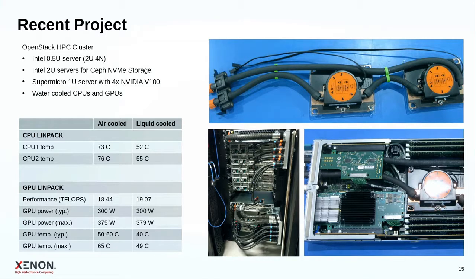We also deployed 1U GPU servers with NVIDIA V100 GPUs. Running LINPACK there, we got slightly better performance with the liquid-cooled solution. Typical power consumption is around 300 watts, with maximum power consumption - since GPUs can temporarily go higher - almost 380 watts per package. GPU temperatures were 15 to almost 20 degrees lower than in an air-cooled solution.